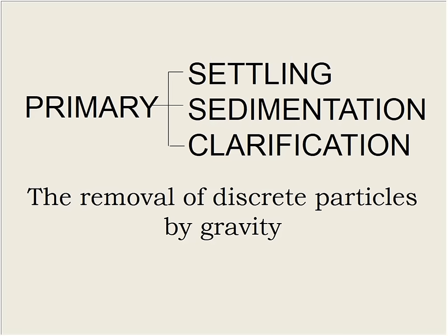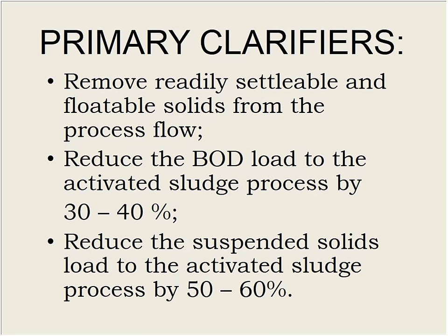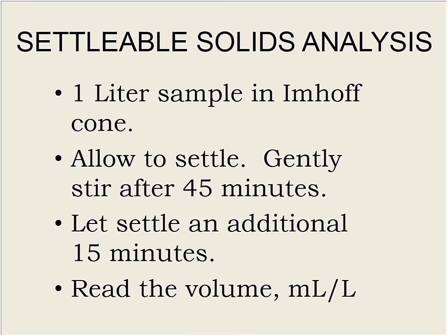So, these terms all mean the same thing: settling, sedimentation, clarification. The settling of discrete particles by gravity. So we're going to remove readily settleable solids. We're going to reduce our BOD by some percentage, 30-ish. We're going to take some of our suspended solids out during this process, too. So that's what's going to happen in this step.